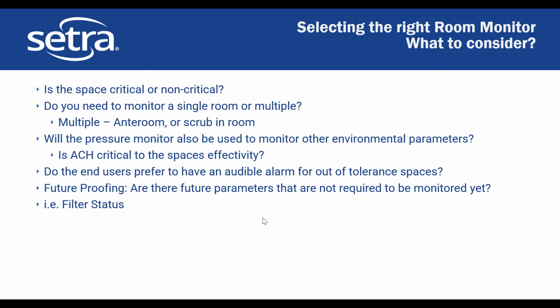Do the end users prefer to have an audible alarm for out of tolerance spaces? This is always a bit of a debate. An audible alarm is not required by the standards that we've talked about today, but it is often desired by the actual end user so that they know about it, even if they're not standing next to it and seeing it visually. The standards require visual indication for most of these spaces, but not audible.